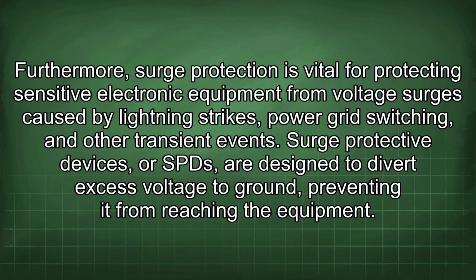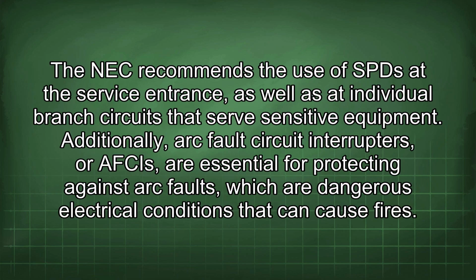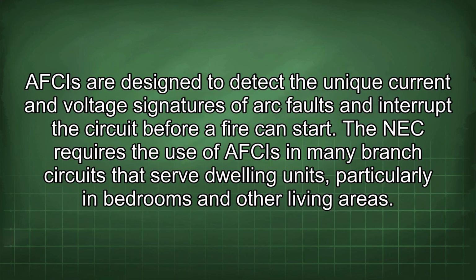the electrical system. Furthermore, surge protection is vital for protecting sensitive electronic equipment from voltage surges caused by lightning strikes, power grid switching, and other transient events. Surge protective devices, or SPDs, are designed to divert excess voltage to ground, preventing it from reaching the equipment. The NEC recommends the use of SPDs at the service entrance, as well as at individual branch circuits that serve sensitive equipment. Additionally, arc fault circuit interrupters, or AFCIs, are essential for protecting against arc faults, which are dangerous electrical conditions that can cause fires. AFCIs are designed to detect the unique current and voltage signatures of arc faults and interrupt the circuit before a fire can start. The NEC requires the use of AFCIs in many branch circuits that serve dwelling units, particularly in bedrooms and other living areas.